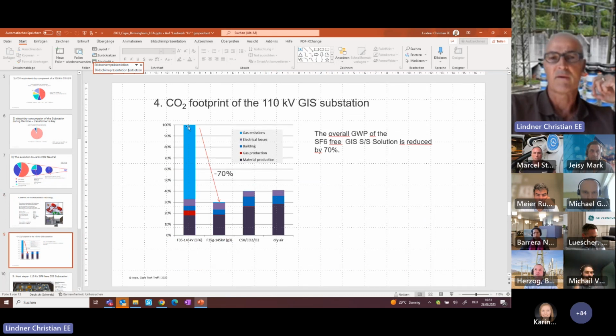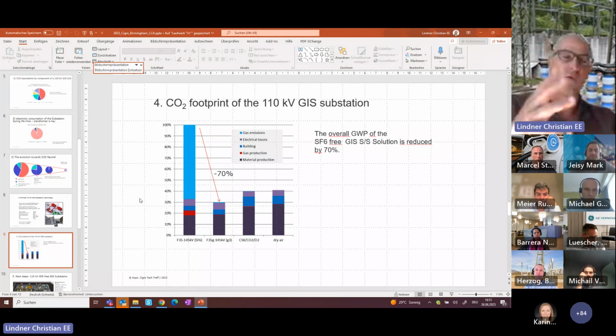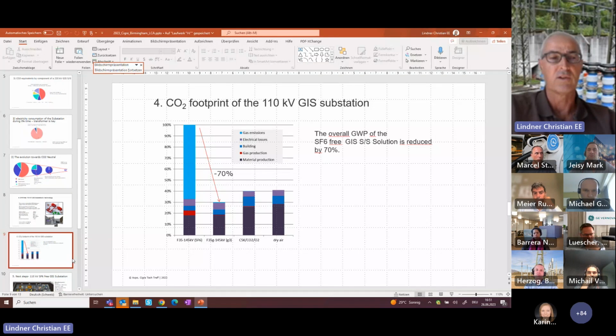At that time, compared to an SF6 solution, the SF6-free solution had a major reduction in the CO2 footprint for this substation. There are no transformers considered in this LCA analysis, but nevertheless, as we have seen before, SF6 is more than 50% responsible for the CO2 footprint of your substation, and this you can really get rid of.